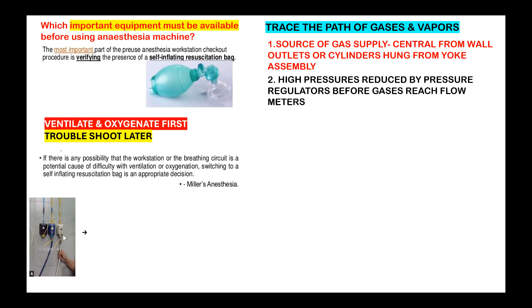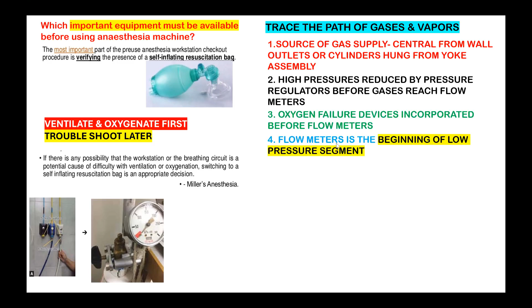Sir, we have to check the central supply, the pipeline pressures. Check the pressure gauge, whether the pipeline or cylinder is available or not. Open the cylinder and see the pressure, and there should always be a reserve available. Okay, so check the cylinder is available. And then third is oxygen failure devices, hypoxic guard testing, as I told earlier. Then you go to the flow meter, the beginning of the low pressure segment. Okay? So from here you go to the flow meter.